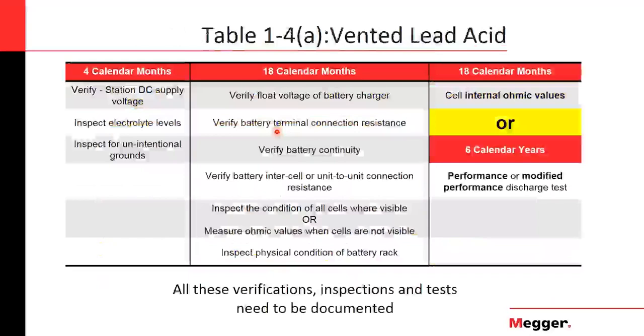So the main thing is to review these tables, this time-based program, which was developed based on regular standards that the industry has for battery maintenance. So table 1.4 is really like 5 tables, or 6 tables, they go from A to F. And the very first table, table 1.4A, is for vented lead-acid batteries. Here we can see that there are 3 periods in which you need to perform maintenance. And the very first one is every 4 calendar months. Every 4 months you should verify the station DC supply voltage.